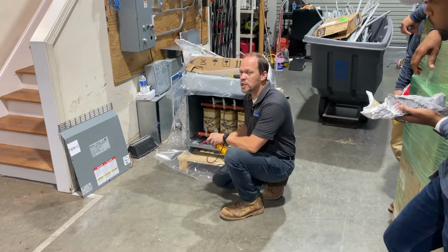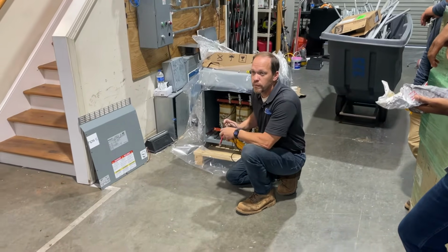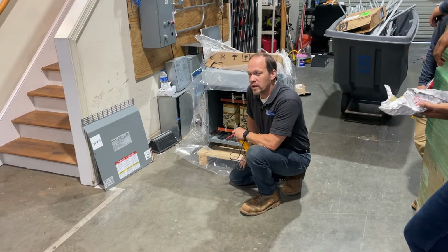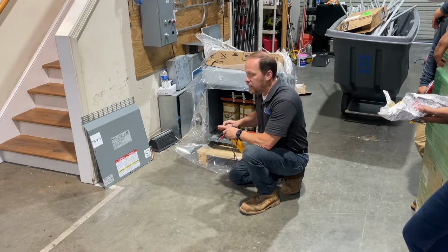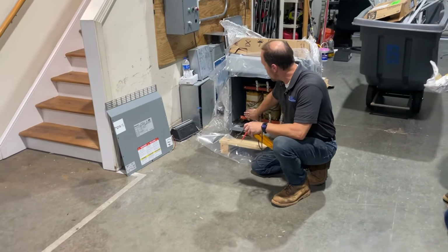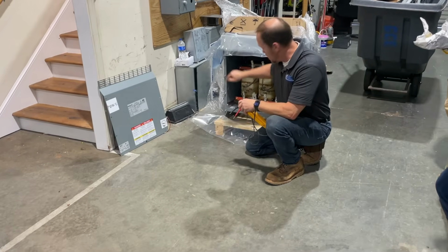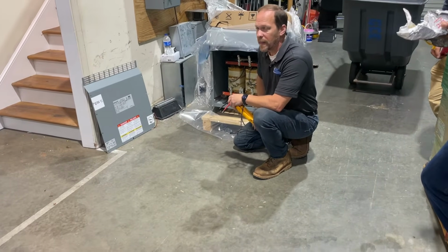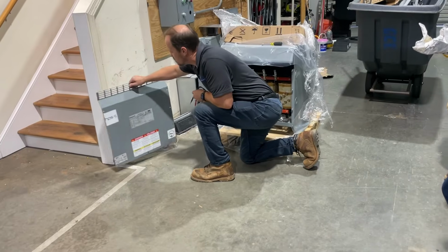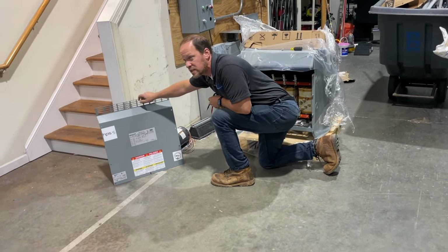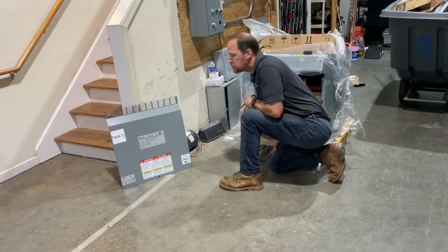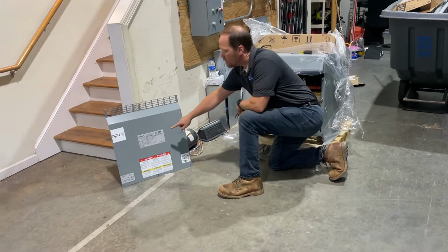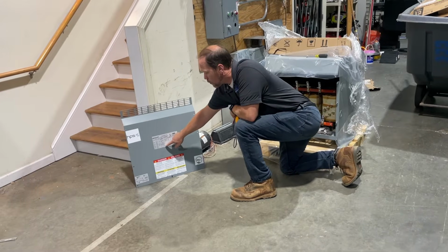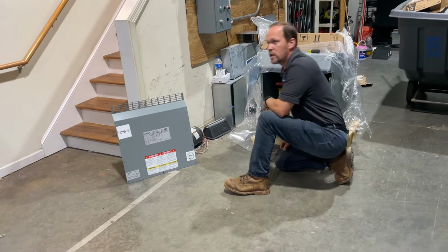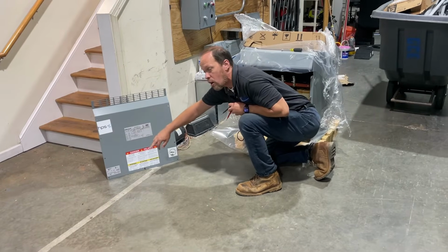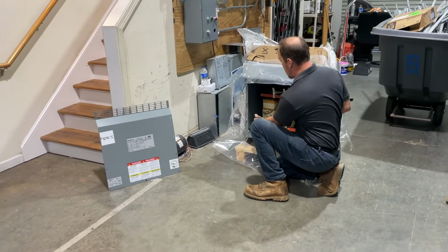All right. Does anybody want to explain any part of this about why? No? Okay. So we talked about this. All this is a winding. It's a piece of wire. It comes from this terminal right here, wraps around the magnet, and comes over to this terminal right here. If you look, you guys aren't going to be able to see it, but there's a diagram right here that tells you that's exactly what's happening. On this particular one, there's a diagram that shows H1 connected through the coil to the center tap, which is HO. And then from H1 to H3, it's also connected through that center tap. So that's why you have continuity between all of those.